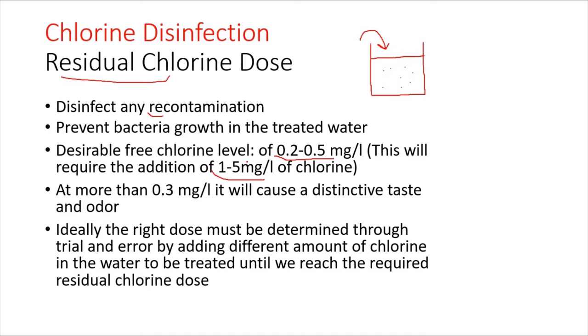Some of that chlorine will be consumed as the chlorine demand dose, and the amount that remains in the water is known as the residual chlorine. At more than 0.3 milligrams per liter, chlorine will cause a distinctive taste and odor, so we will feel the presence of the chlorine. We have to stay at a level less than 0.3 milligrams per liter.